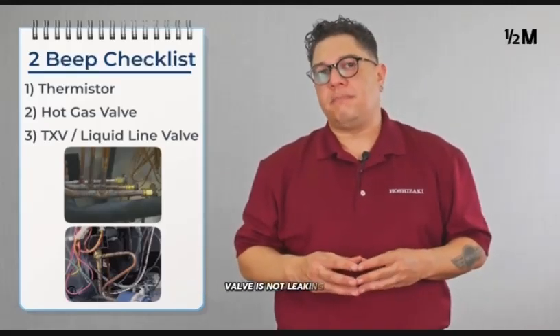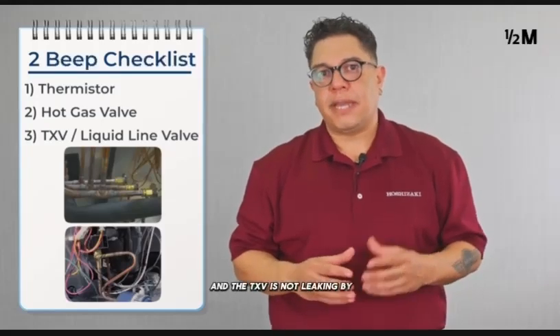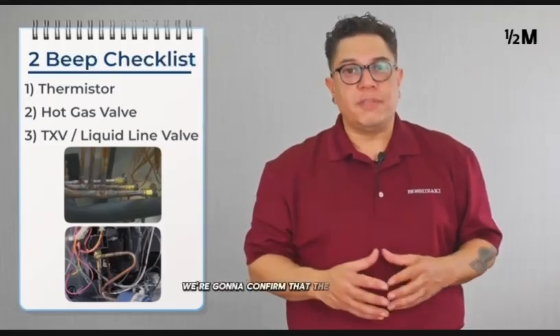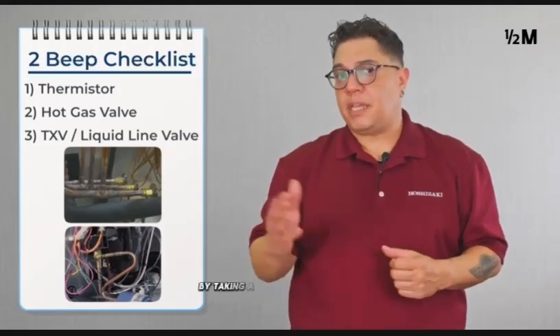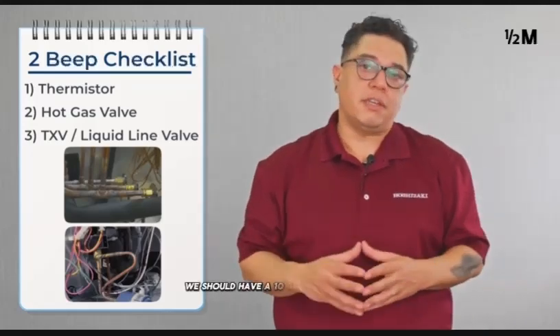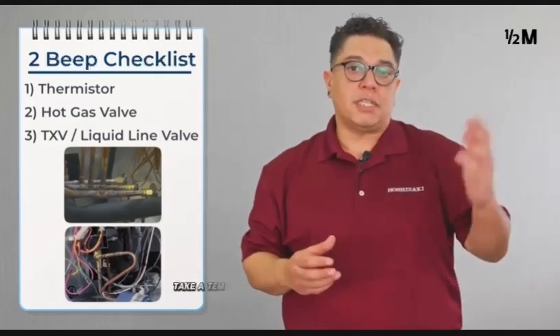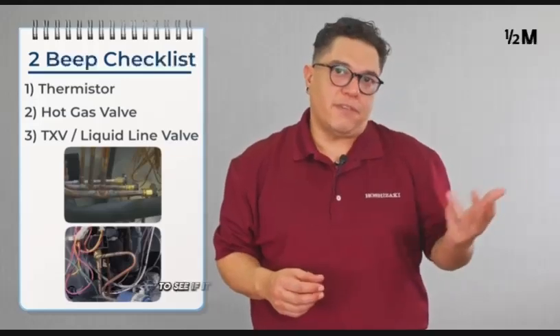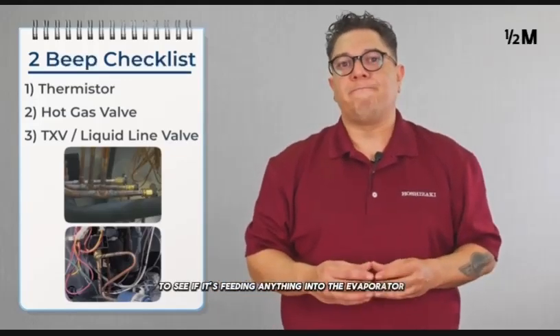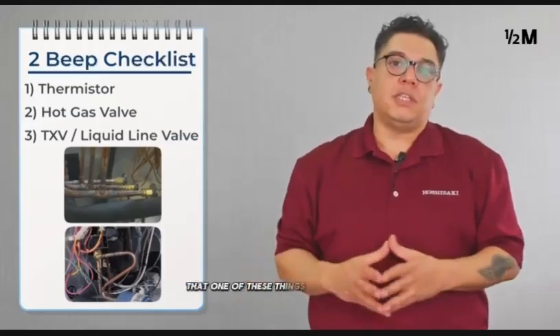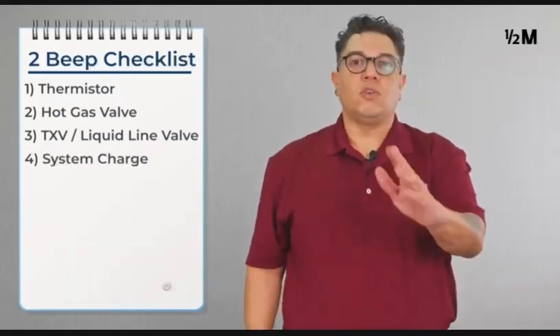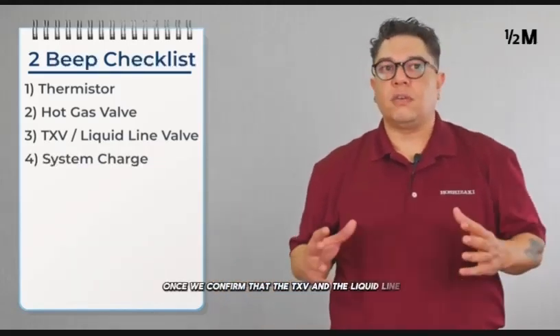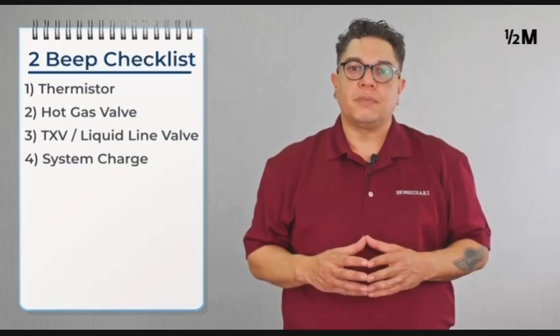Next step, we need to confirm that the liquid line valve is not leaking by and the TXV is not leaking by during harvest. We're going to confirm that the liquid line valve is not leaking by taking a temperature across it. We should have a 10-degree differential. And we're going to take a temperature on the outlet of the TXV to see if it's feeding anything into the evaporator. There is a possibility that one of these things is the problem. If it is leaking by, we are replacing the part. Once we confirm that the TXV and the liquid line valve are not leaking by, we're going to move on to a low charge scenario.